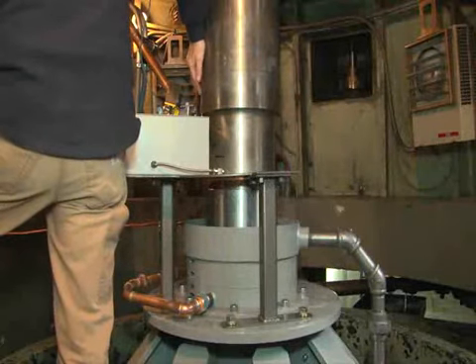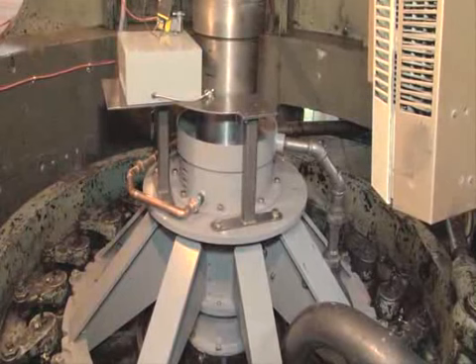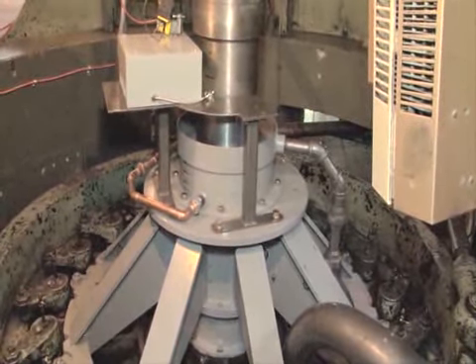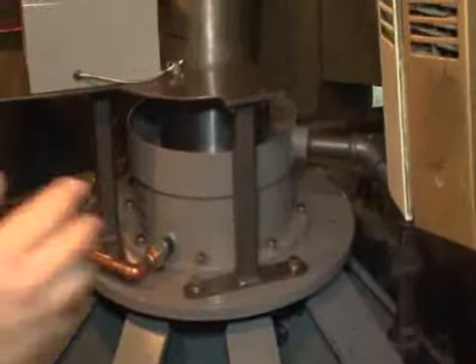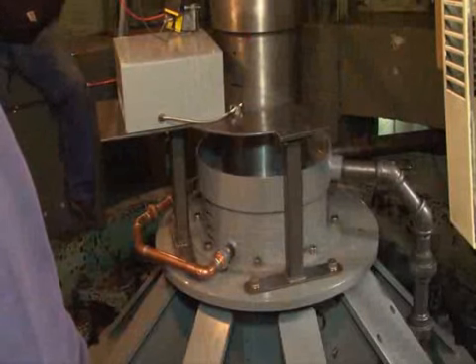Engineers and turbine operators have always been concerned about the risk of wiping a metallic or rubber-type bearing due to loading or lack of lubrication. And destroying a bearing on startup is something no one wants to face. Water-lubricated, high-modulus elastomer bearings, however, tend to be more tolerant of a marginally lubricated start than the higher-friction rubber bearings sometimes used. The operators are anxiously awaiting the start.